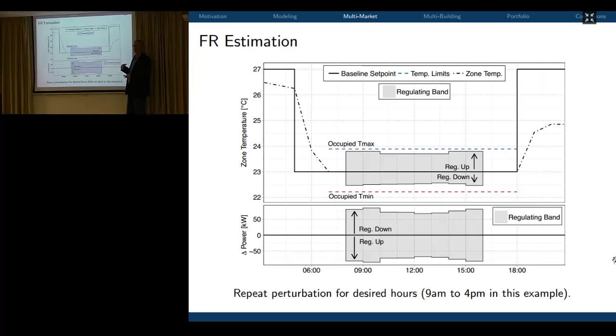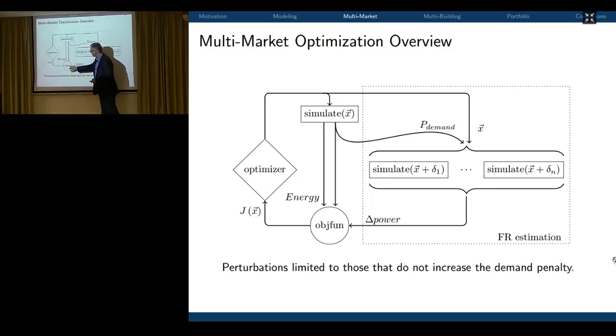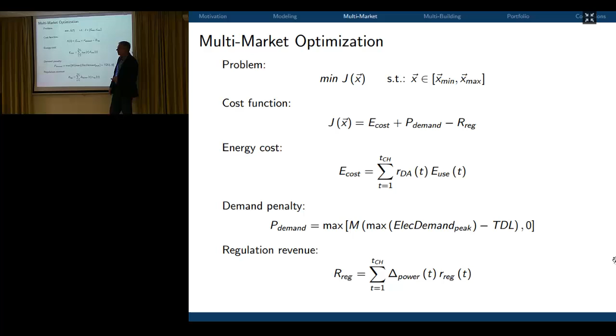In this multi-market optimization, I'm looking at a particular control variable, for a particular building peak demand, and I take the control vector for the next 24 hours. This is a vector of controls, and I change and look at a number of perturbations around that set point—a baseline strategy, x, with deltas around it. The baseline strategy, which I'll show next, will not be constant. I look at these perturbations and keep the one that minimizes the objective function, which also considers the regulation revenue.